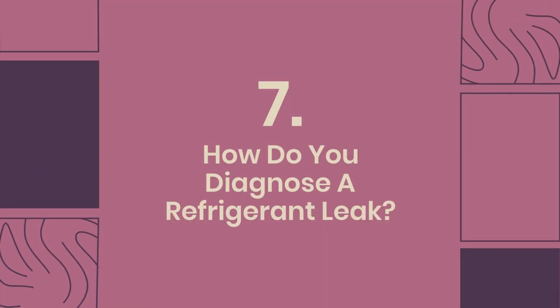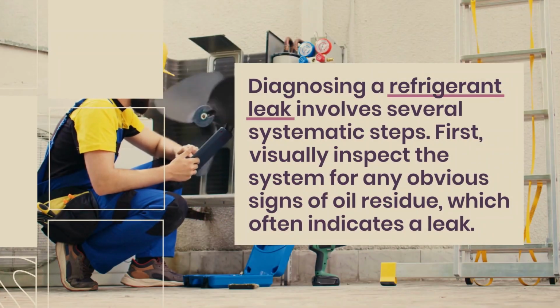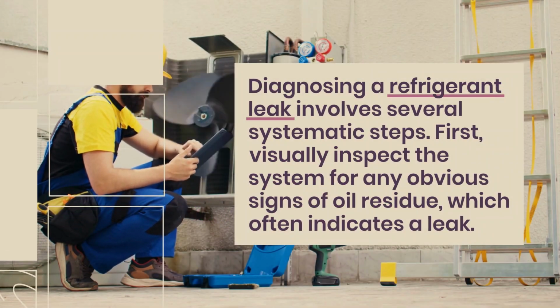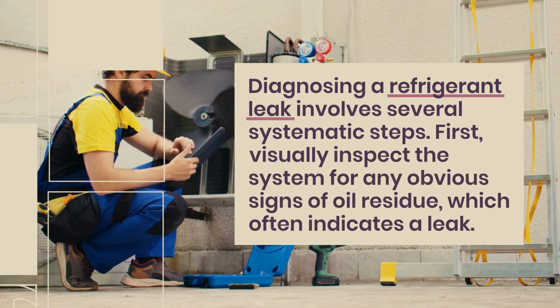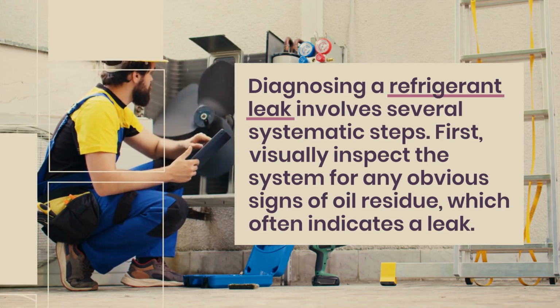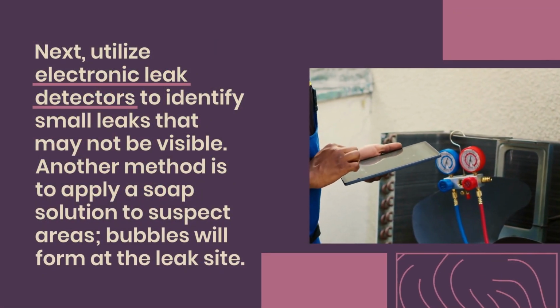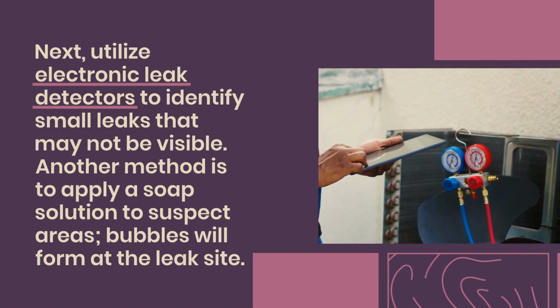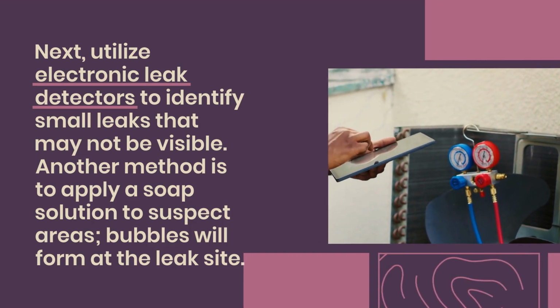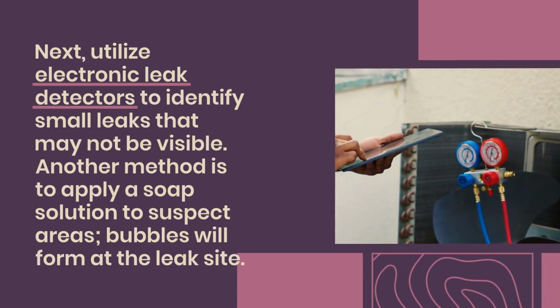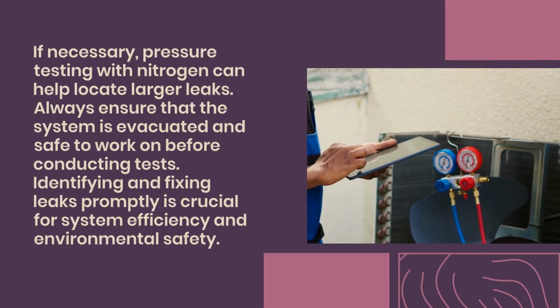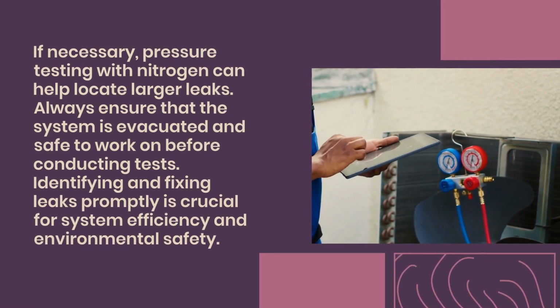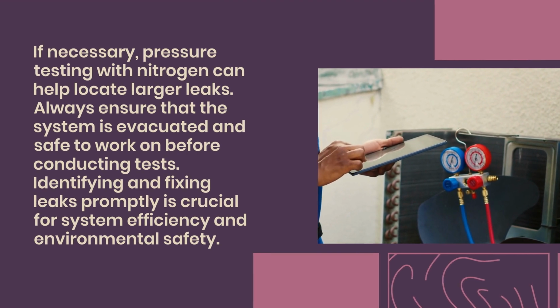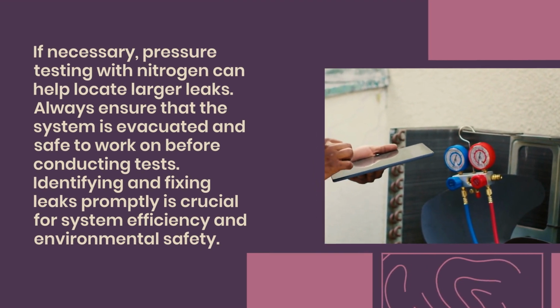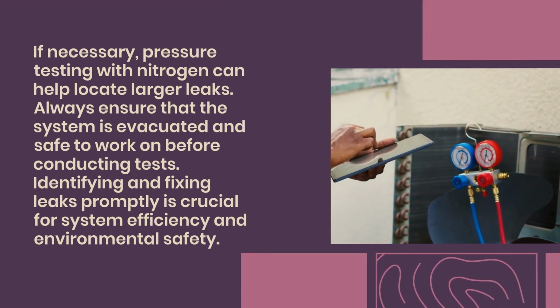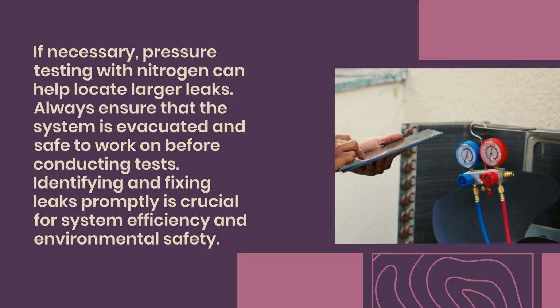7. How do you diagnose a refrigerant leak? Diagnosing a refrigerant leak involves several systematic steps. First, visually inspect the system for any obvious signs of oil residue, which often indicates a leak. Next, utilize electronic leak detectors to identify small leaks that may not be visible. Another method is to apply a soap solution to suspect areas. Bubbles will form at the leak site. If necessary, pressure testing with nitrogen can help locate larger leaks. Always ensure that the system is evacuated and safe to work on before conducting tests. Identifying and fixing leaks promptly is crucial for system efficiency and environmental safety.